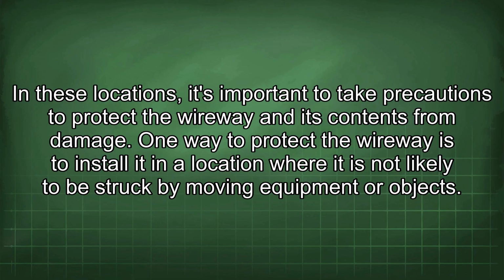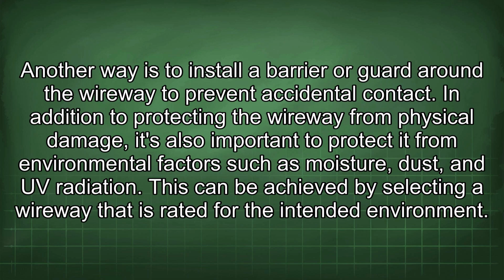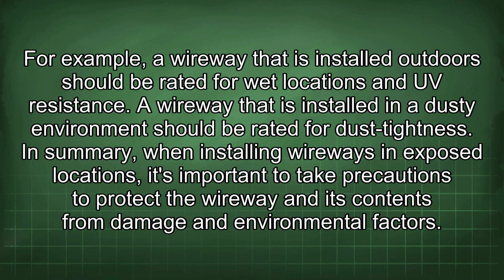One way to protect the wireway is to install it in a location where it is not likely to be struck by moving equipment or objects. Another way is to install a barrier or guard around the wireway to prevent accidental contact. In addition to protecting the wireway from physical damage, it's also important to protect it from environmental factors such as moisture, dust, and UV radiation. This can be achieved by selecting a wireway that is rated for the intended environment. For example, a wireway that is installed outdoors should be rated for wet locations and UV resistance. A wireway that is installed in a dusty environment should be rated for dust tightness.